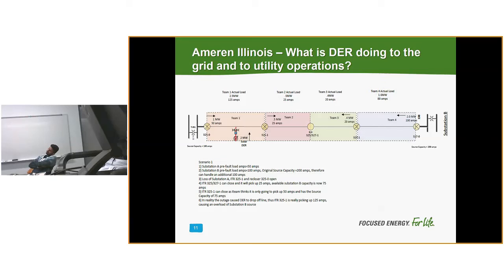This DER here that was producing energy was masking the true load that was here. The true load that I've got on this section is not 50 amps. It's 50 amps plus whatever the DER was producing and picking up. Does that make sense? In reality, when I have the outage, this will drop offline. There's no voltage source for the solar farm anymore. It will come offline; 1547 will force it to come offline anyway, right? And I have 125 amps on this section in reality, not 50 amps. So that was masking an additional 75 amps.